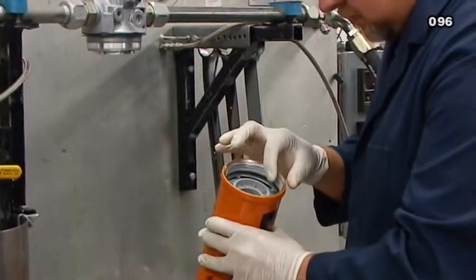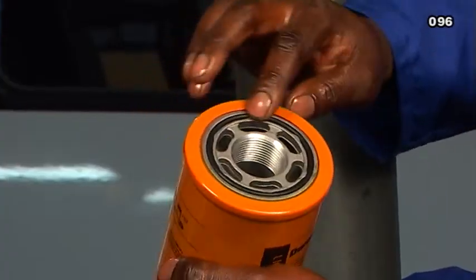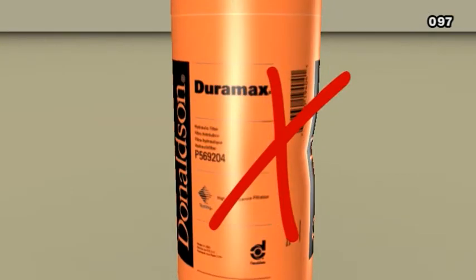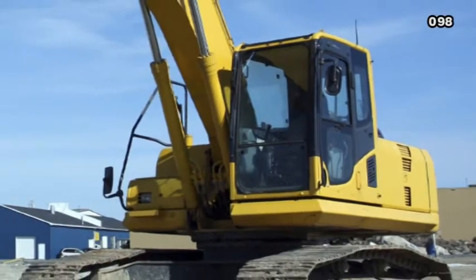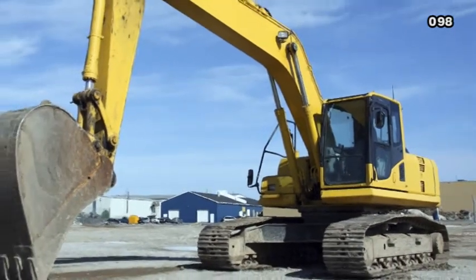Secondly, check the new filter you will be installing for any shipping or handling damage. Do not install a dented filter since the canister has been weakened at that point. Thirdly, be sure the system is turned off and that there is no pressure present.